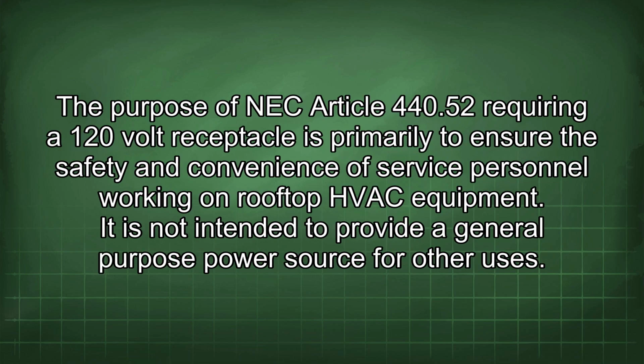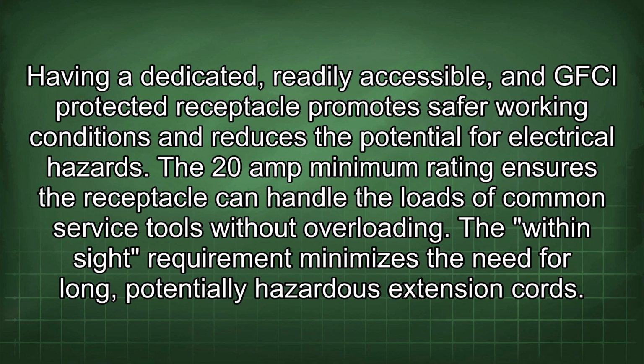The purpose of NEC Article 440.52 requiring a 120-volt receptacle is primarily to ensure the safety and convenience of service personnel working on rooftop HVAC equipment. It is not intended to provide a general-purpose power source for other uses. Having a dedicated, readily accessible, and GFCI-protected receptacle promotes safer working conditions and reduces the potential for electrical hazards.